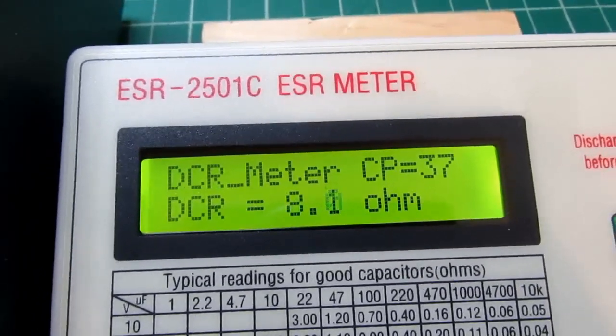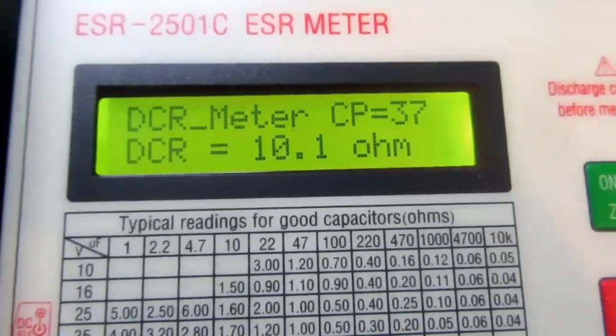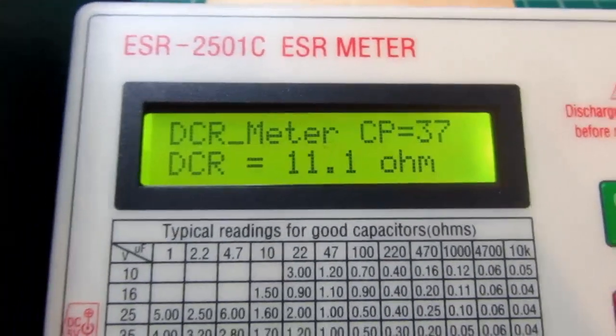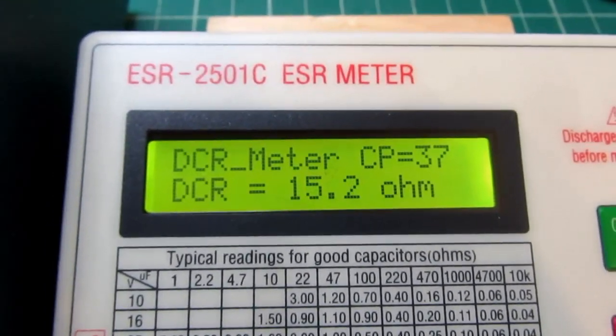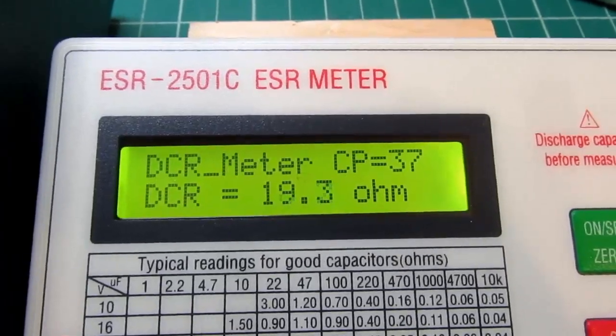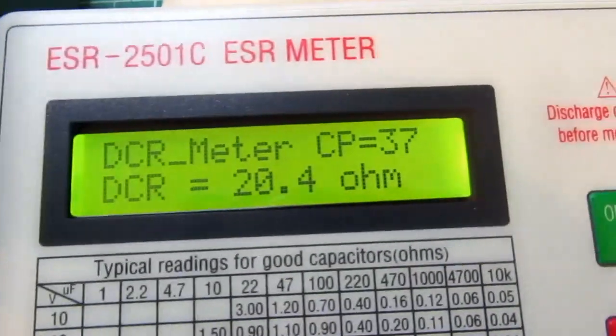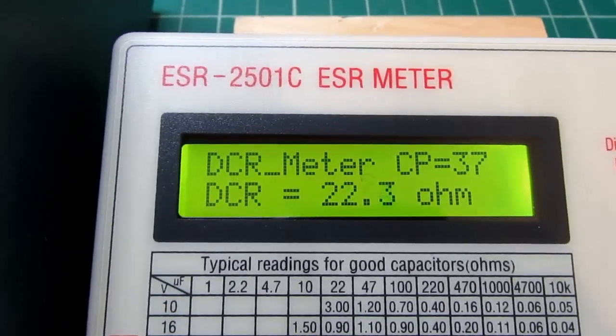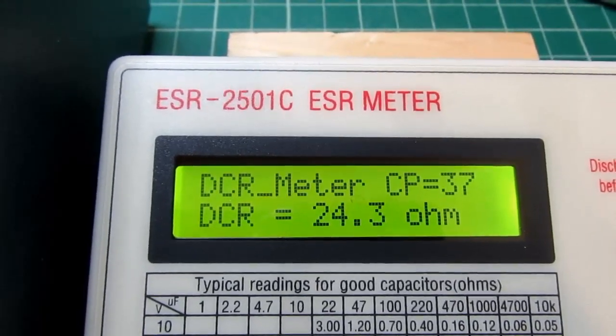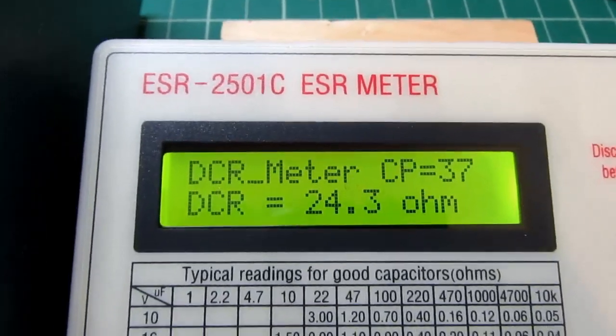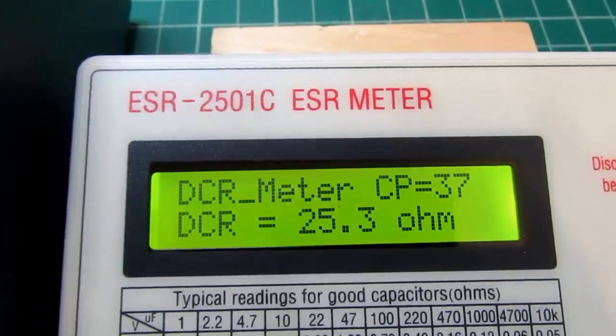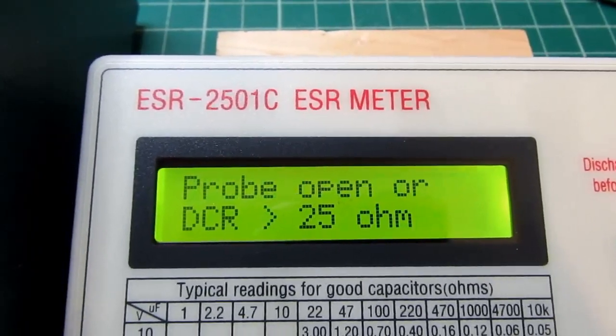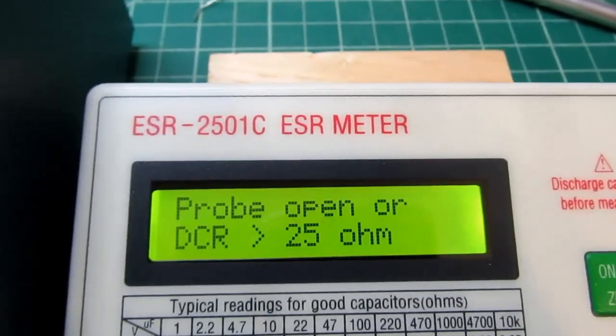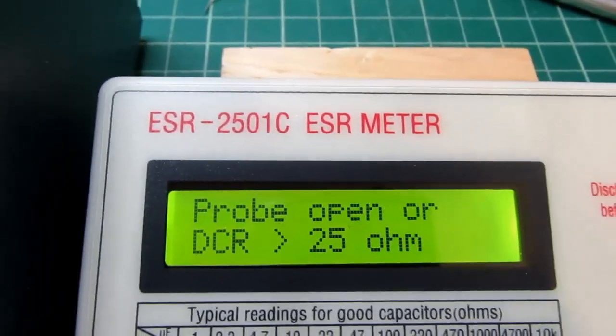So 7, 8, 9, back up to 10 ohms, then 11 through 19, up to 20, then 21, 22, 23, 24 - when I go to 25 it'll actually be 25 point something, so it should overrange. Well, it made it up to 25.3. Now it overranged when I went beyond that. So it can read slightly higher than 25, but not 26.